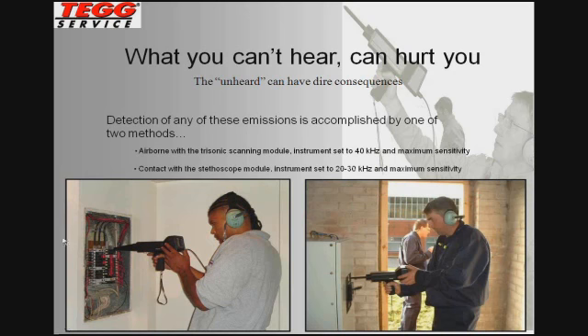The stethoscope module, as you know, becomes a sound wave guide, and it's a method of channeling the sound waves into the instrument when there's a medium in between where the source of the emission may be and the instrument itself. Some examples of that may be molded-case circuit breakers, enclosed bus duct, liquid-filled transformers, anything where there's a medium in between the instrument and where the emission may be occurring. The optimal frequency there, as you know, is 20 to 30 kilohertz, and we typically begin at 25 kilohertz and tune the instrument from there as we identify any types of anomalies.